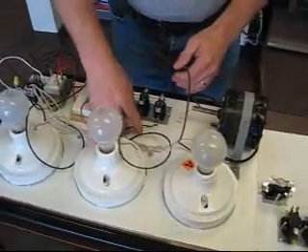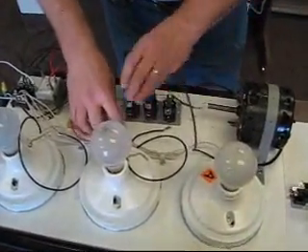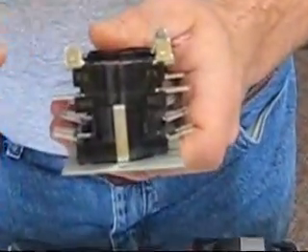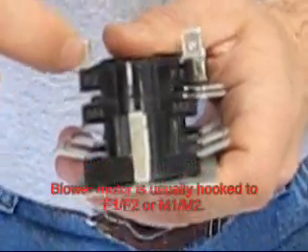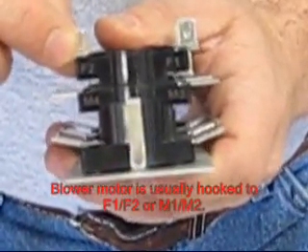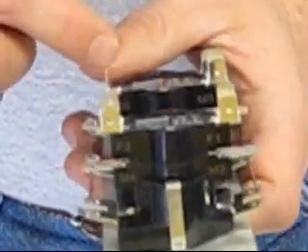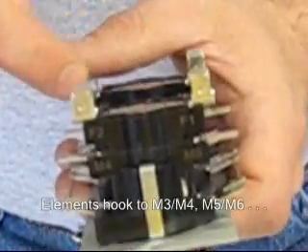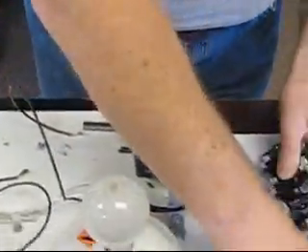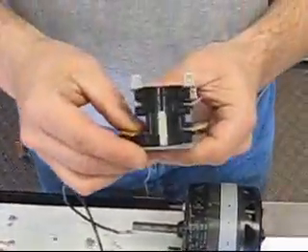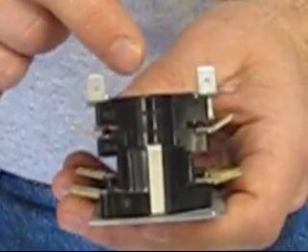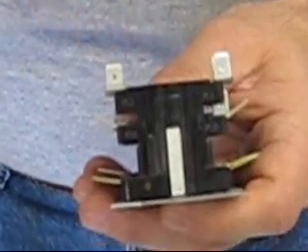It's not rocket science to hook wires to a sequencer. Let's take a look at the numbers here. This one has an F1 and an F2. That's where your blower motor hooks up to. Followed by M3, M4, M5, M6. Basically you just hook your elements across from each other to the numbers. And let's look at this one. This one doesn't have the F but the M1 and M2 act the same as an F1 and F2. They just use M's and leave out the F's.